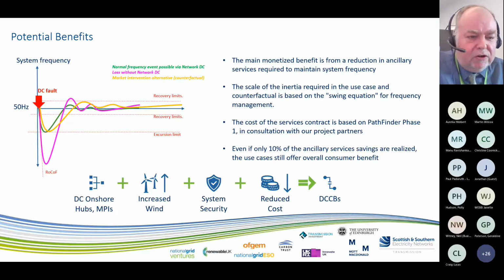Then within a couple of seconds, if you'd installed high-speed switches within the arrangement, particularly a full bridge arrangement, you would be able to bring back the power. But a couple of seconds is an eternity in frequency response. Frequency response is delivered from about 1 second onwards, the fastest of the frequency response available.